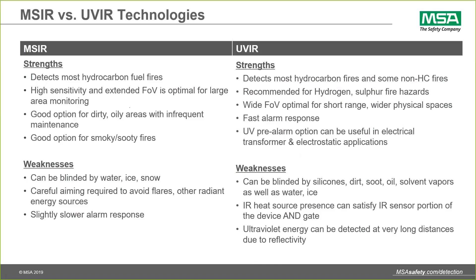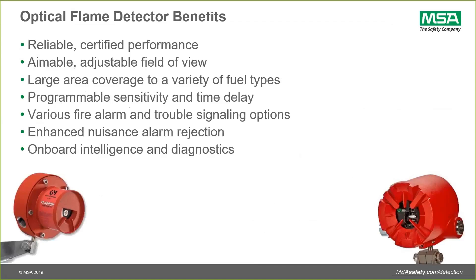That's a quick summary, but both provide significant benefits: reliable, certified performance; the ability to adjust the field of view or aim it to where fire is most likely to occur; coverage of a significantly large area for a variety of different fuel types; programmable sensitivity and time delay options; different signal types including 4-20mA, relay outputs, Modbus, and HART; enhanced false alarm rejection; and onboard intelligence diagnostics for end users.